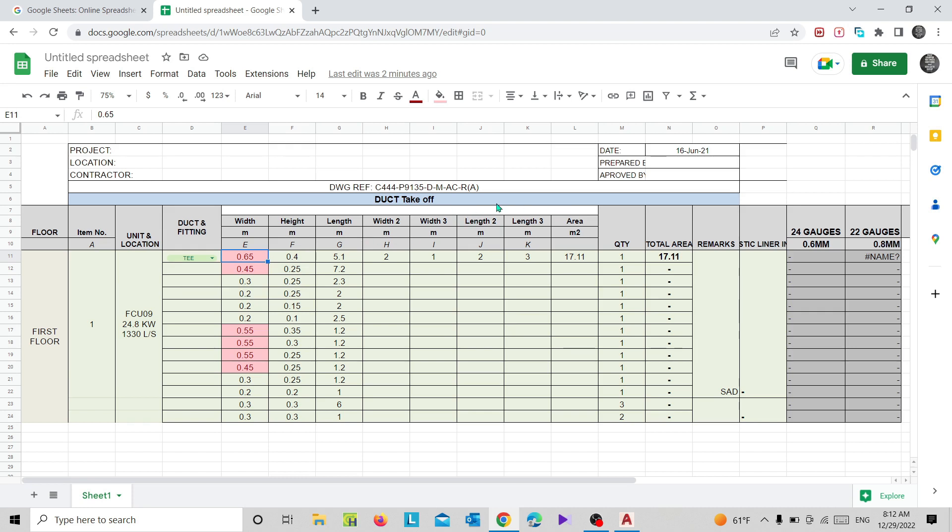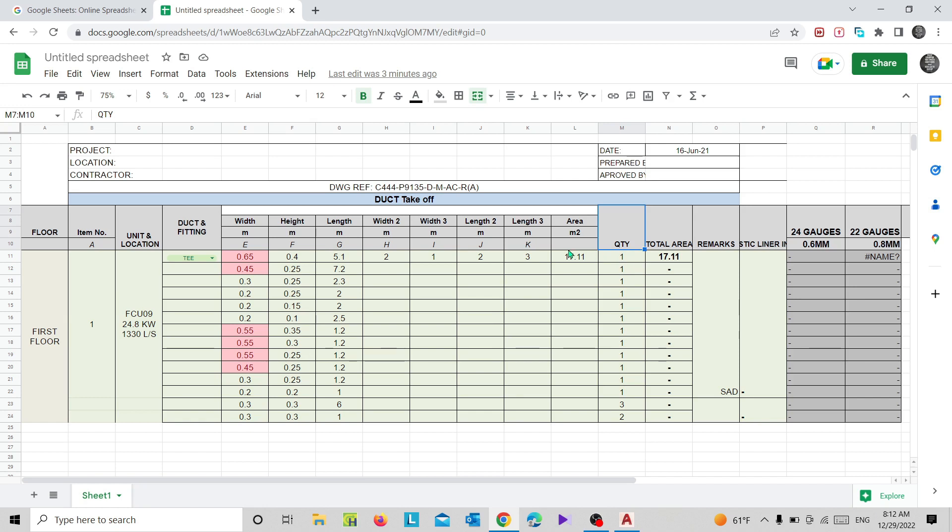As per the formula, you can mention the value on the prospect itself and you can get the answers on the area section. We have area in here and we have quantity. As we all know, each duct piece has the length of 1.2 meters. So if the length exceeds 1.2 meters, you can simply mention how many quantities you need.